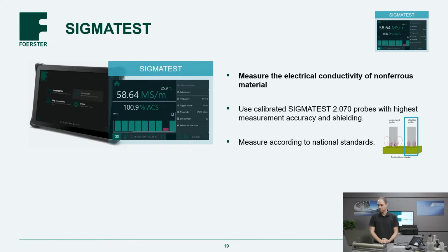So Sigma Test is an application for measuring the electrical conductivity of non-ferrous material. For that we use calibrated probes of our Sigma Test 2070, which is really known in the market for the highest measurement accuracy, and shielded probes. The probes are so well shielded that you can really measure directly on the material's edges and not have an effect of this on the measurement. And very important for measuring the electrical conductivity, we fulfill the national standards, and that's very important for a measurement system.